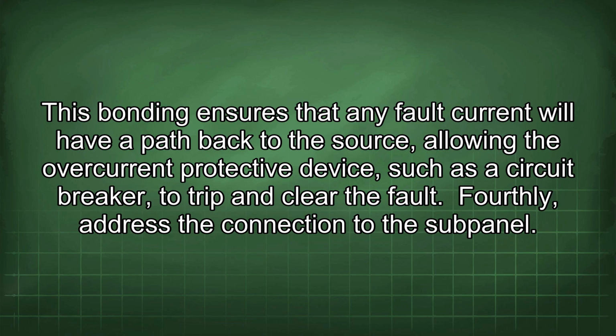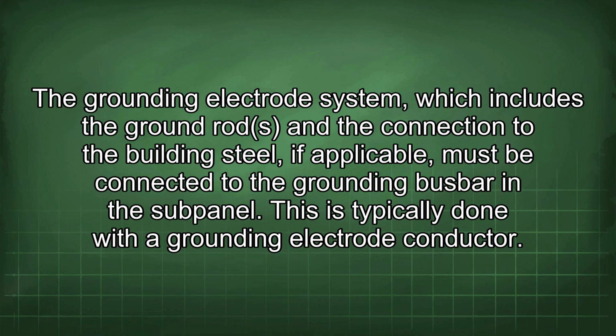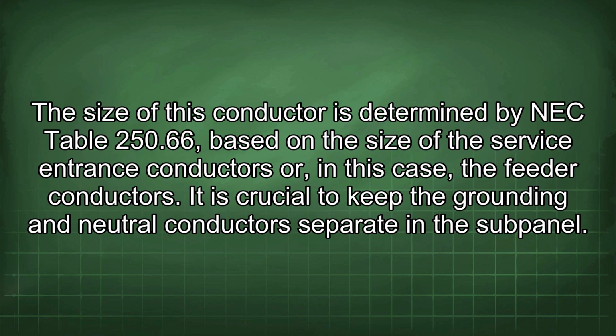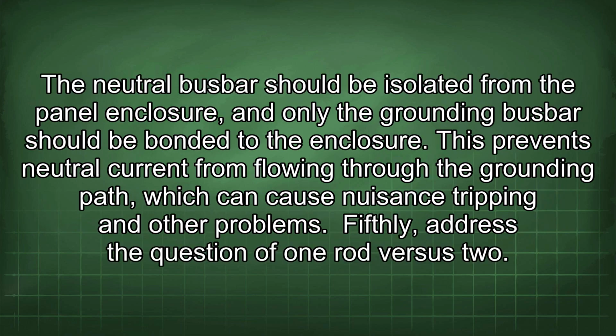Fourthly, address the connection to the subpanel. The grounding electrode system, which includes the ground rods and the connection to the building steel, if applicable, must be connected to the grounding busbar in the subpanel. This is typically done with a grounding electrode conductor. The size of this conductor is determined by NEC Table 250.66 based on the size of the service entrance conductors, or, in this case, the feeder conductors. It is crucial to keep the grounding and neutral conductors separate in the subpanel. The neutral busbar should be isolated from the panel enclosure, and only the grounding busbar should be bonded to the enclosure. This prevents neutral current from flowing through the grounding path, which can cause nuisance tripping and other problems.